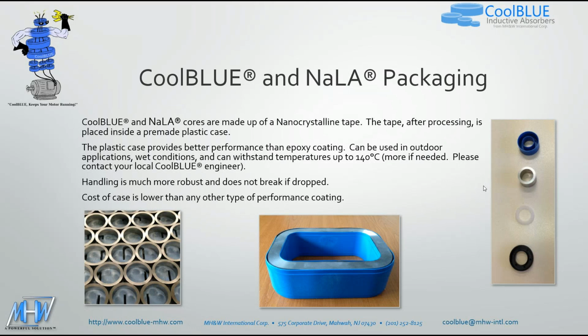So the CoolBLUE and the NALA cores, they're actually installed inside of a plastic pre-made case. The material inside of them is what they call nanocrystalline tape ribbon. It's a type of metal that's actually doing the absorption of this high frequency energy. The plastic case actually has a better performance than epoxy coatings. The other way to protect the metal cores is to basically put an epoxy coating on there, but that tends to be more expensive, and we find that the plastic case is a better solution.